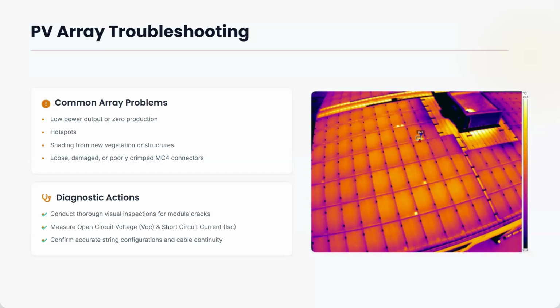So those two measurements as part of the diagnostic actions will tell you something, and they will direct you to where to go. Because if you are getting low currents, it could be a disconnect or a partial contact or a breaking out of terminals like MC4 connectors or there, or a cable has cut and is partially touching or is touching another place.